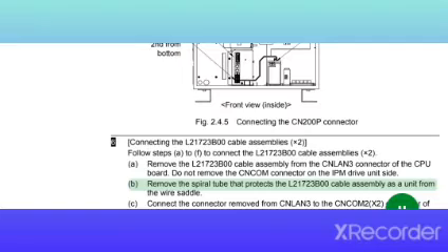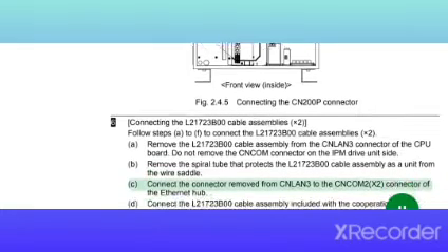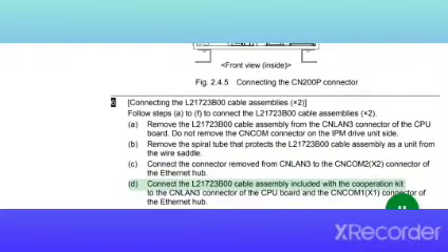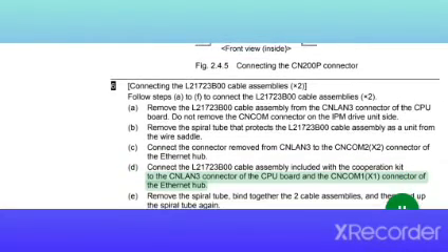Remove the spiral tube that protects the L21723B00 cable assembly as a unit from the wire saddle. C. Connect the connector removed from CNLAN 3 to the CNCOM2 (X2) connector of the Ethernet hub. D. Connect the L21723B00 cable assembly included with the cooperation kit to the CNLAN 3 connector of the CPU board and the CNCOM1 (X1) connector of the Ethernet hub.